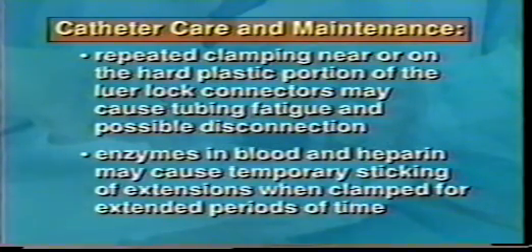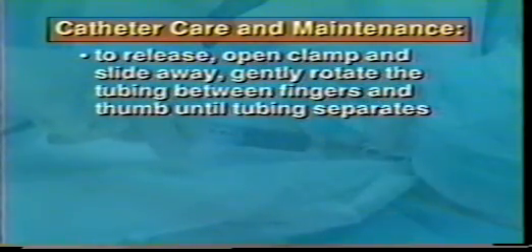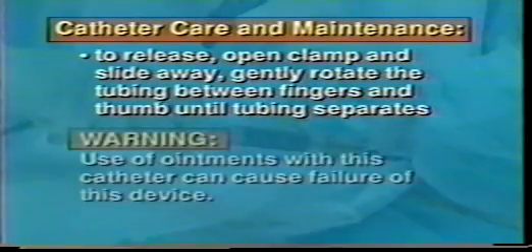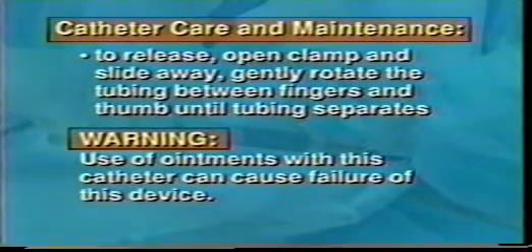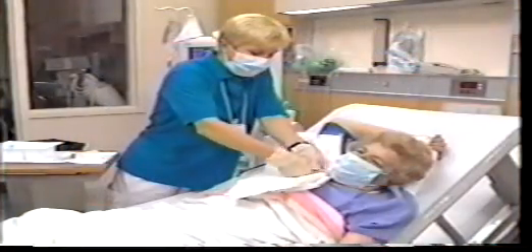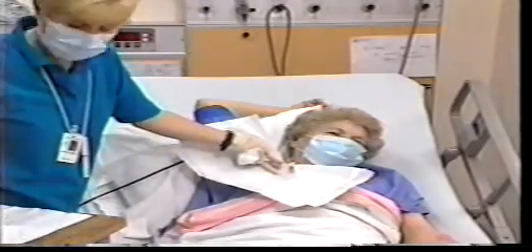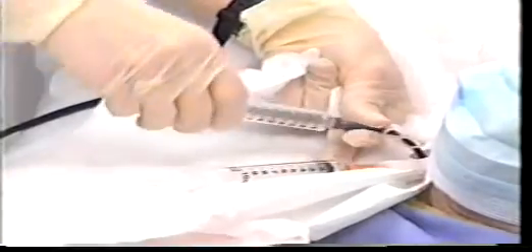Enzymes in blood and heparin may cause temporary sticking of extensions when clamped for extended periods of time. To release, open clamp and slide away, gently rotating the tube between the fingers and thumb until tubing separates. Warning: use of ointments with this catheter can cause failure of this device. Approximately 5 cc of blood is withdrawn from each limb and discarded. A minimum of 10 cc's of normal saline is used to flush each limb of the catheter prior to the connection to the dialysis circuit.